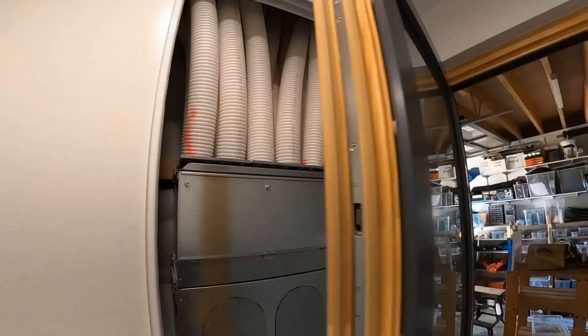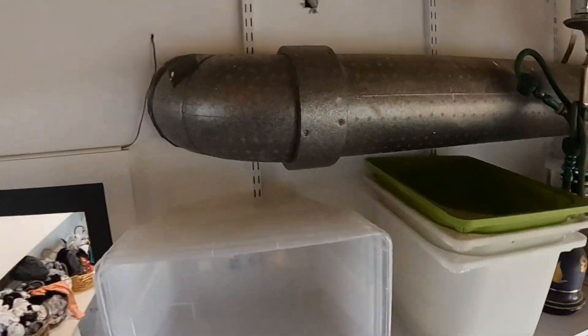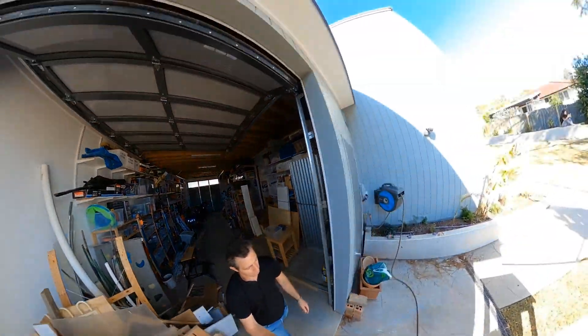This is a special HEPA filter cassette. I can open those thumbscrews and insert a HEPA filter during a bushfire to remove all the particulate pollution. Here's a walk around — that's the outside air intake duct; it's insulated and goes out to the side of the house through the shed, and you can see the intake grill there where air comes into the MVHR unit.